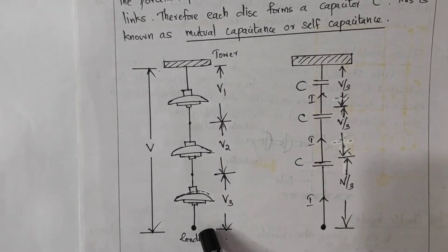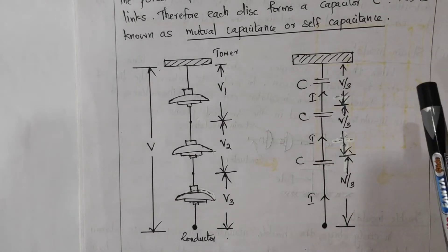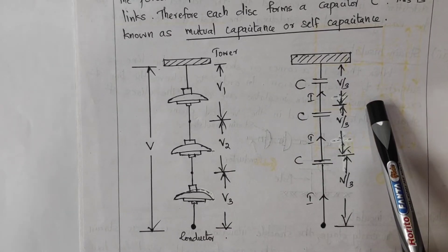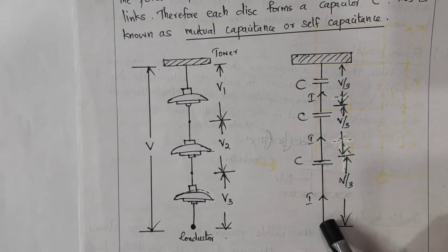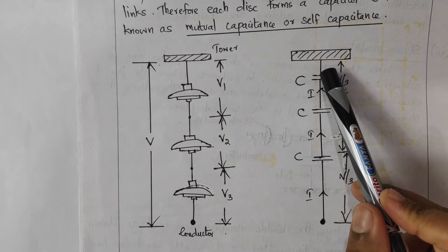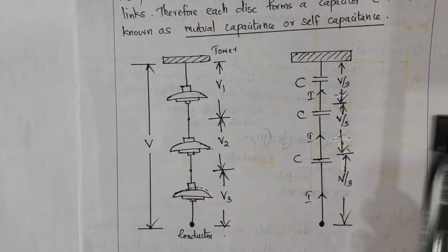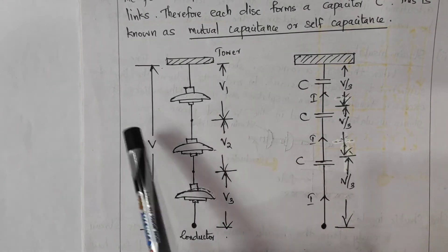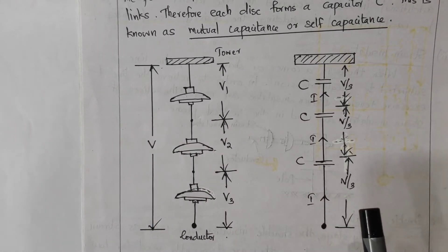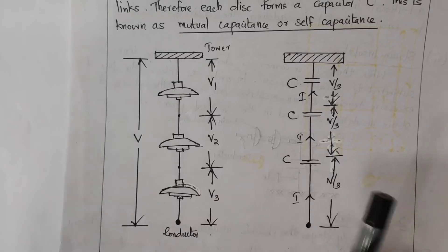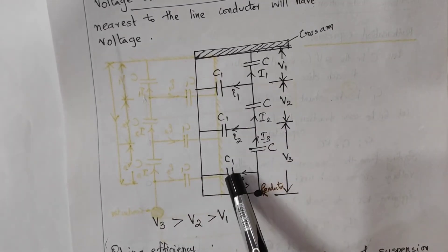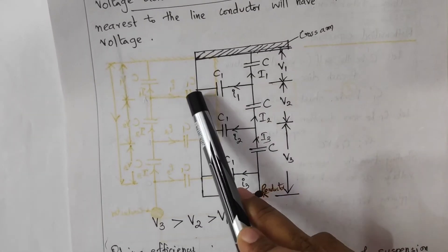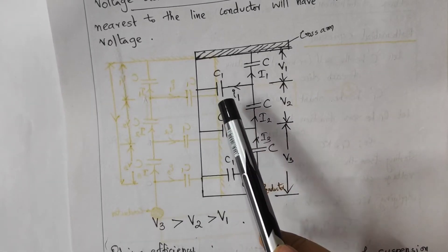If the total voltage across this string is V, the voltage distribution across each capacitor would be V by 3, and current from the conductor flows accordingly. However, in actual cases, there will be shunt capacitance also — that is, between the metallic link and the tower there forms a capacitor called the shunt capacitance, denoted C1.